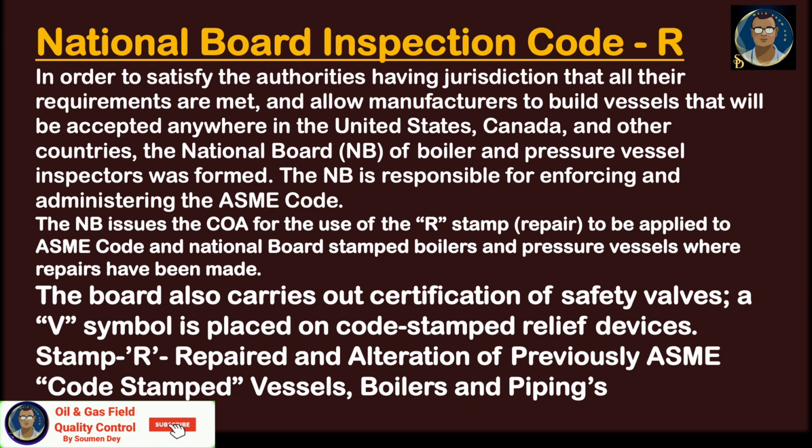The NB issues a COA for use of the R stamp, which stands for repair, to be applied to ASME code and National Board stamped boilers and pressure vessels where repairs have been made. The board also carries out certification of safety valves. A V symbol is placed on code stamped relief devices. Stamp R: repair and alteration of previously ASME code stamped vessels, boilers and piping.